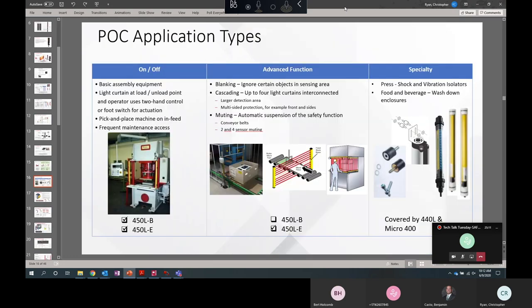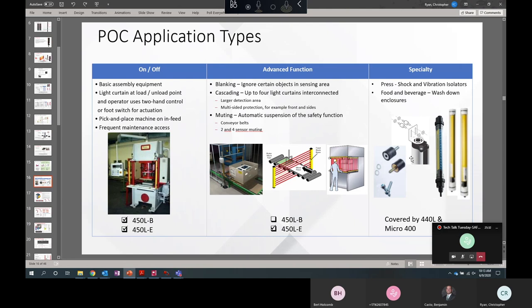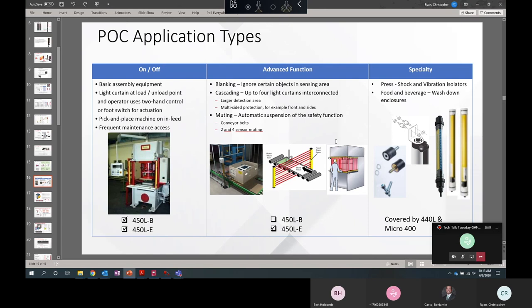The types of POC applications. B and E can both be used to do simple on-off applications. B actually only does on-off. You can also accept a reset signal or external device monitoring if you're not going to be using a logic interface or a PLC for your reset and EDM. On the right-hand side over here, we've got specialty applications. So if you've got shock and vibration or if you're in food and beverage and you need a wash-down light curtain, we have other light curtain families for that. We've got the 440Ls and the micro 400s. Nothing at the moment for a 450L, but those will be coming in the future. If you want to do advanced functionality such as blanking, cascading, or muting, you must use the E.